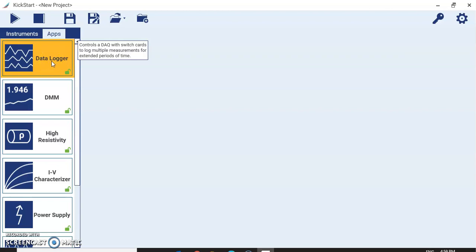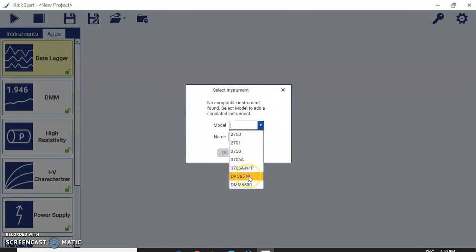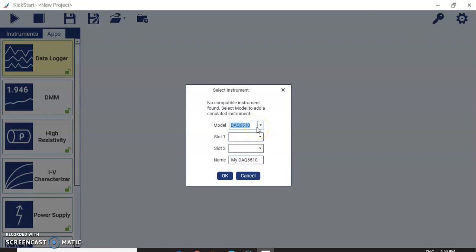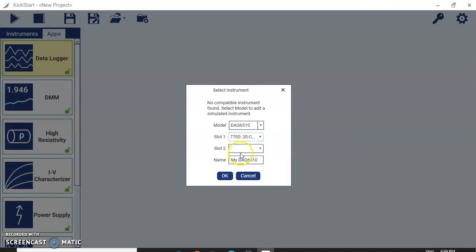Just double-click on Data Logger to launch it. Since I don't have physical equipment right now, I will use the simulated DAQ6510. Keithley's DAQ6510 is a two-slot data logger where you can insert up to two multiplexer cards. Different cards are available: 20-channel, 32-channel, 40-channel. I will use the 7700, which is a 20-channel multiplexer card, and keep slot two open. I will name my device My DAQ6510 and click OK.